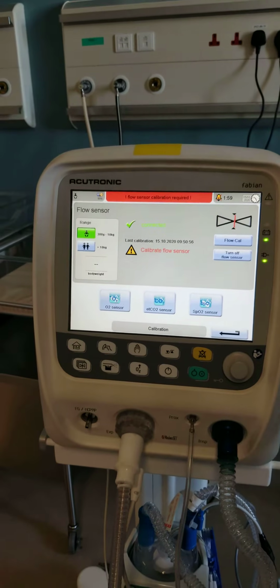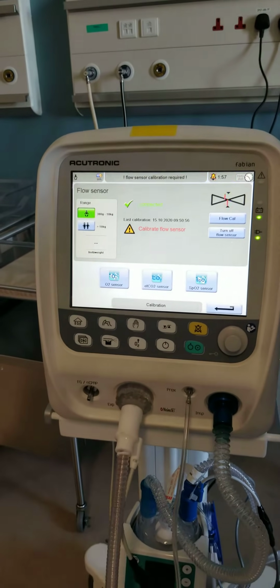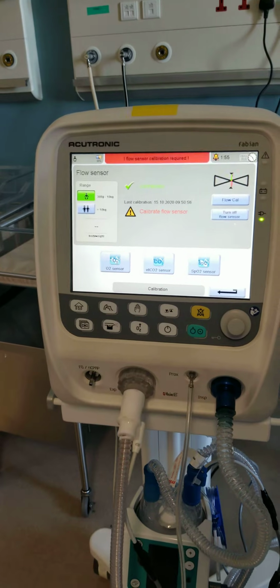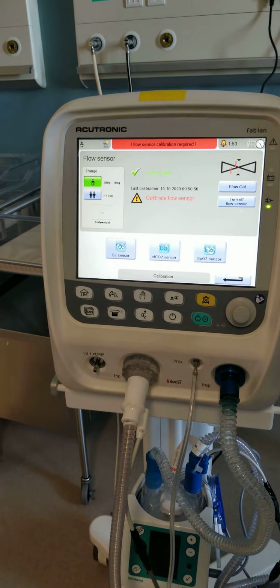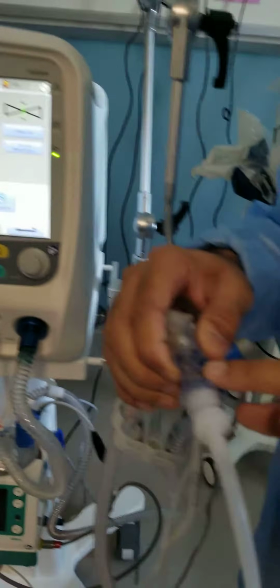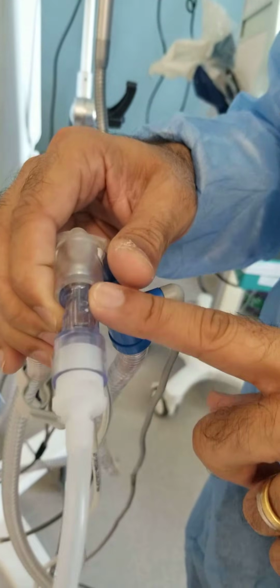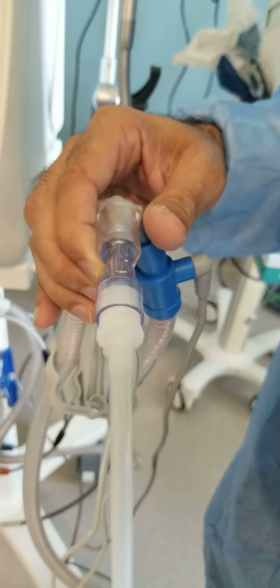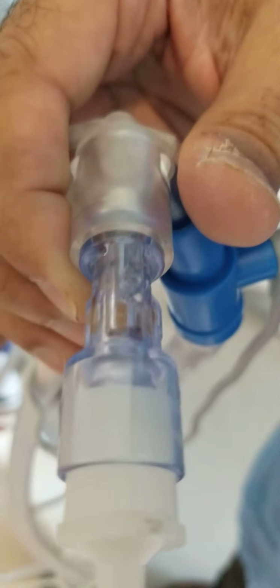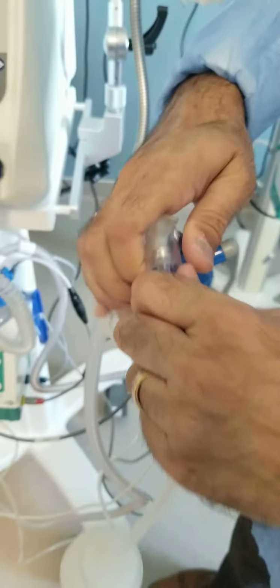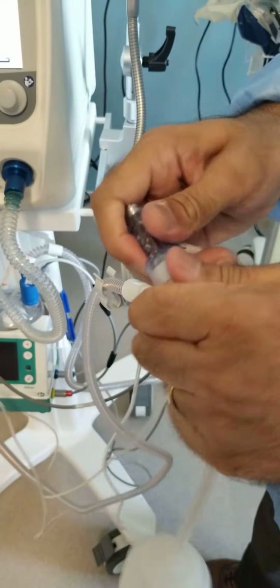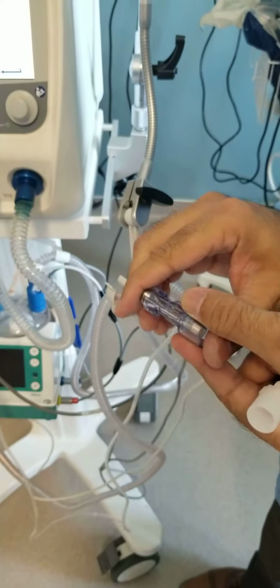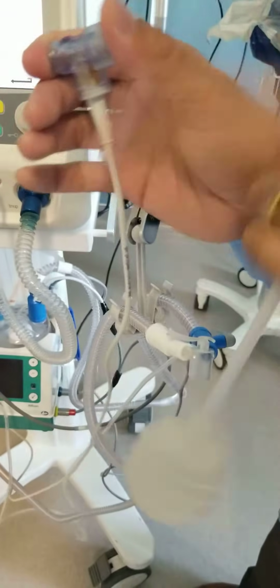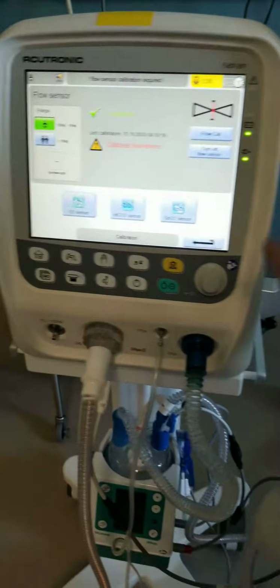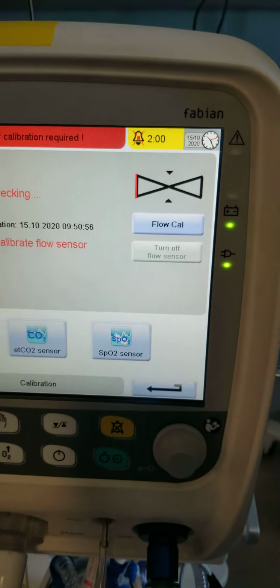The first thing to do in any ventilator is a flow sensor calibration, because you have to calibrate the flow sensor. Flow sensors could be reusable, or in this case it is single use. The purple one is single use. The yellow one is normally the reusable one. To do it is quite simple. I just occlude both sides, of course with sterile gloves. And then I press flow cal.